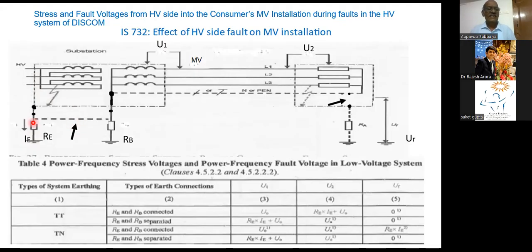Here, there is an interconnection. You can see this is the interconnection between the body and the secondary neutral. See, this is the secondary neutral of the transformer. This is the body. These are interconnected. And here, what is the choice the consumer has? He can either detach his earth electrode and keep it disconnected from the protective earth neutral. This is one option. This is called TT. Suppose this is connected, then it becomes TNS.